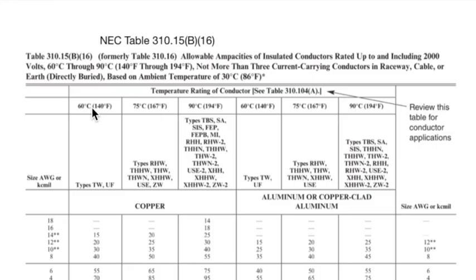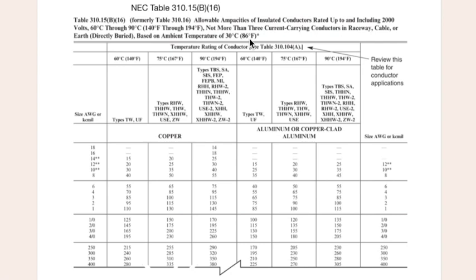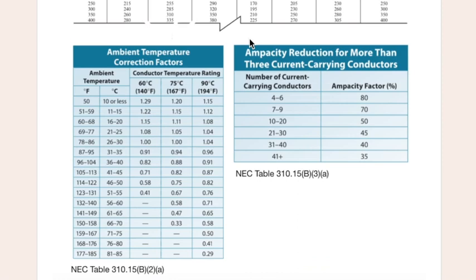Now remember, we can only use this chart to select conductors if we meet all three criteria that list up here, which is that the conductor is good up to 2,000 volts, that there's no more than three current-carried conductors in the raceway, and it's got an ambient temperature of 86 or 30 degrees Celsius. So obviously, since we're discussing correction factor, most of these problems are all going to be for too high a temperature.